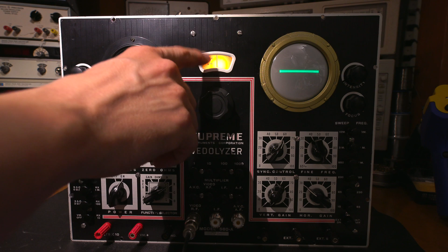So I'll just plug this in here. Right now we're on band D, so that's D right here. You can see the scale here. What I'll do is I'll just turn the brightness down for a moment. You can see on the scale here, it says 210. So I see 230 and then 240, and I want to bring this up to 450. Watch what happens when I get close to 450. See how this is starting to raise up here? Now that's with no gain. So 50 millivolts is a lot of signal.